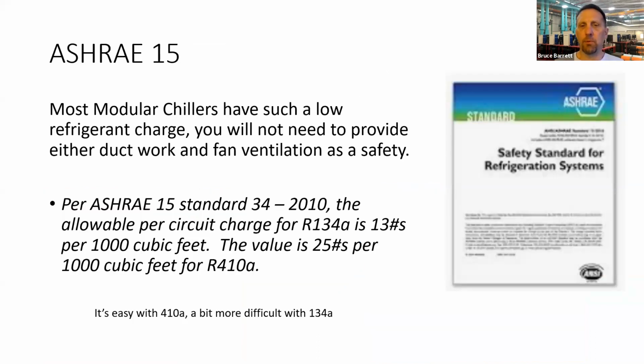All right, the ASHRAE 15 requirement, what is it? Well, for 410A, it's 25 pounds per 1,000 cubic feet in your largest refrigeration circuit. So 410A, I just don't know if there's any math out there that you would ever require refrigerant ventilation or compliance with ASHRAE 15. For 134A, it's 13 pounds per 1,000 cubic feet of equipment room space.